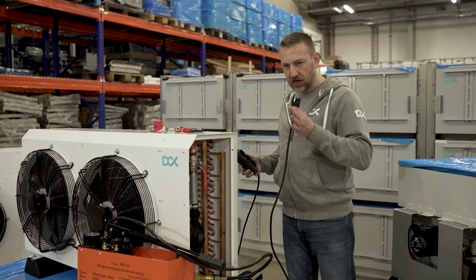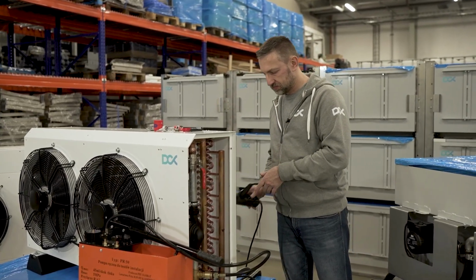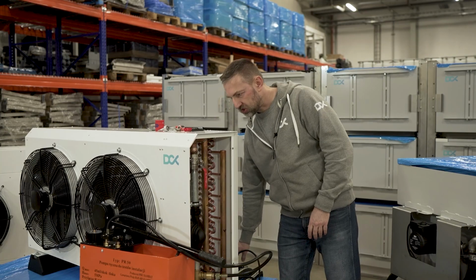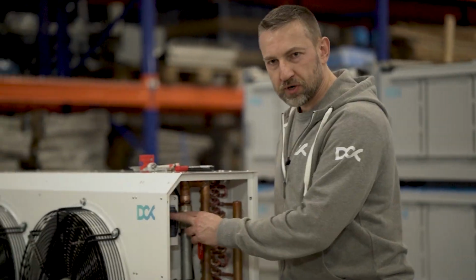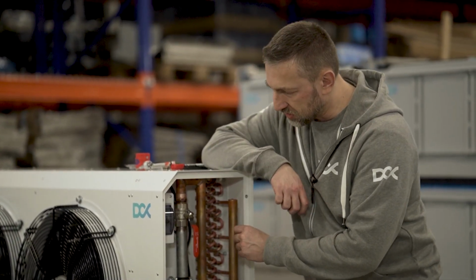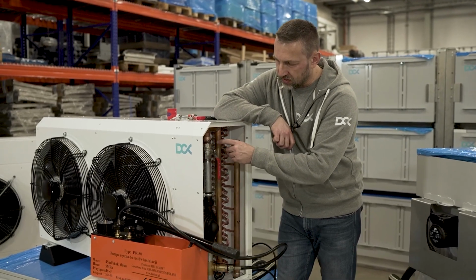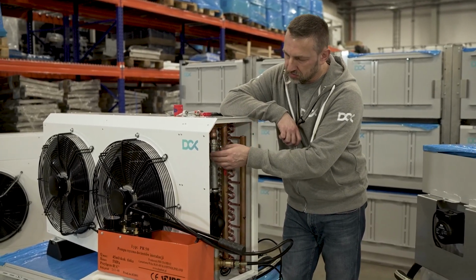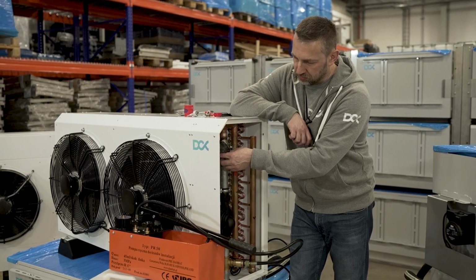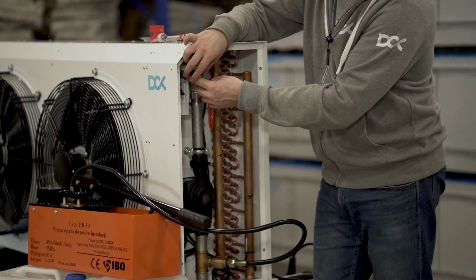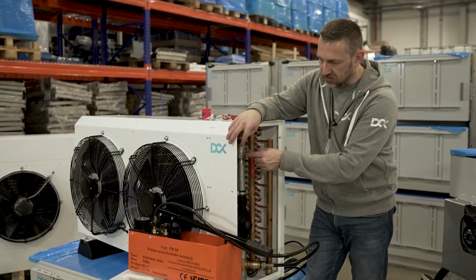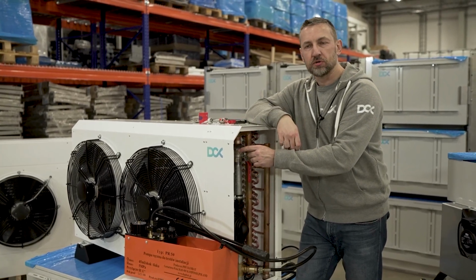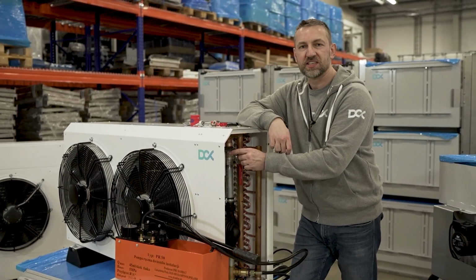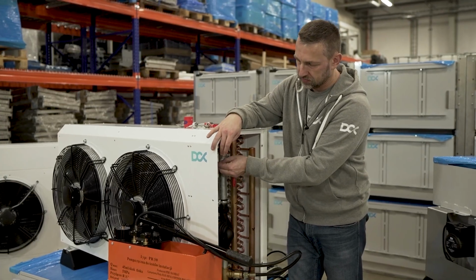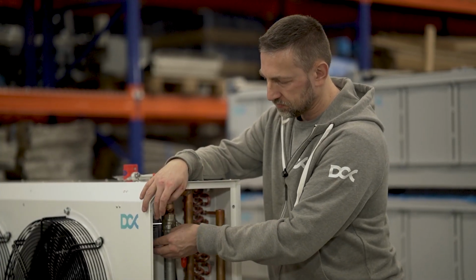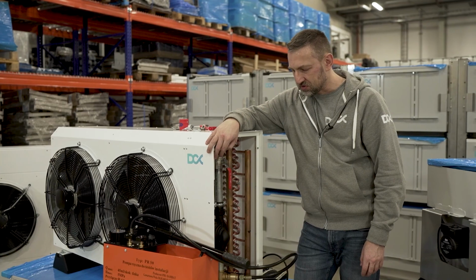So I'm just connecting the unit. Nothing special is required, and I have two breakers here. So just observe those two breakers. One is marked F like fans, or W, and it's for the fan operation. The other one is for the pump. So let's start the pump first, because what you need to do right now is hear the sound of the pump. So let's try to hear it. Starting P like pump, and I can hear that the water is traveling through the system.